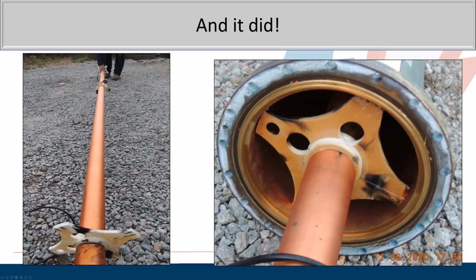Well, they took apart the transmission line. They ended up having to replace about 150 feet of 8-inch rigid. So it was a good catch, and it's a great example of how thermal imaging can catch some things that electronics can't detect.